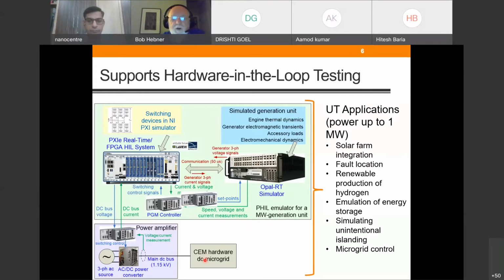We have communications back and forth between the two systems, and we can put physical hardware in as if it were part of a more complex system and do hardware in the loop testing. So we have the 1 megawatt microgrid plus an Opal RT to simulate a power grid, plus the FPGA HIL system that allows us to look at the power electronics.